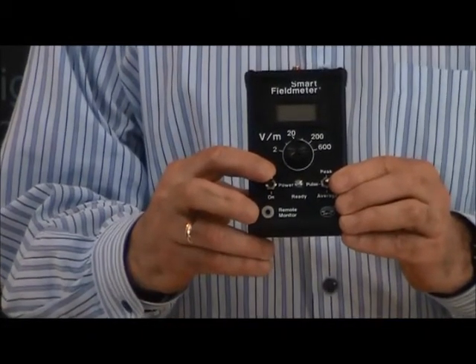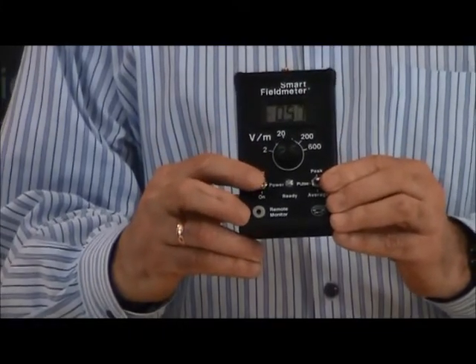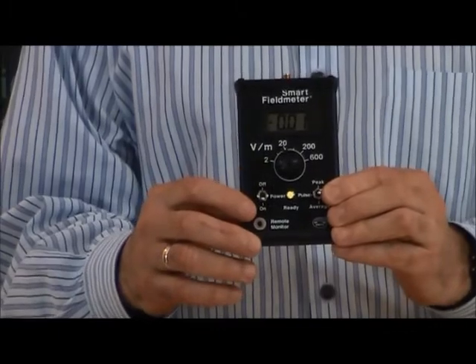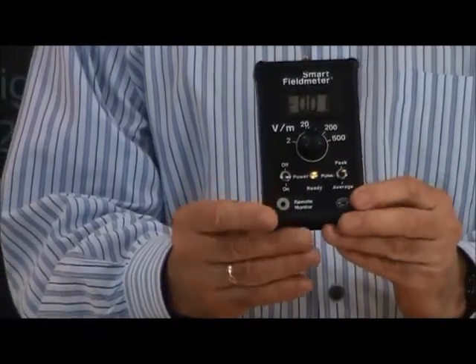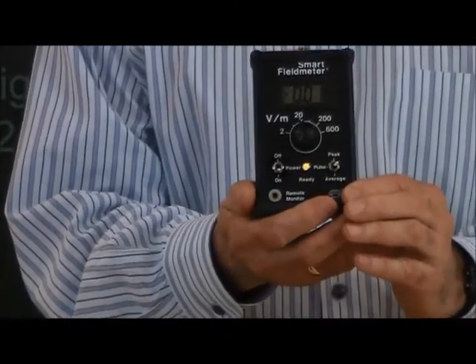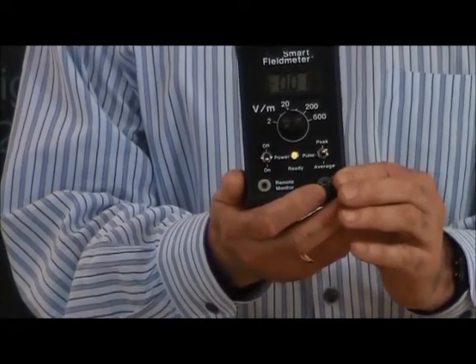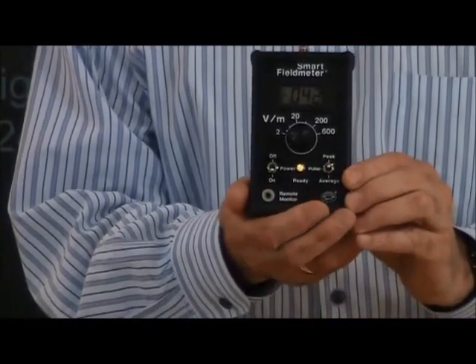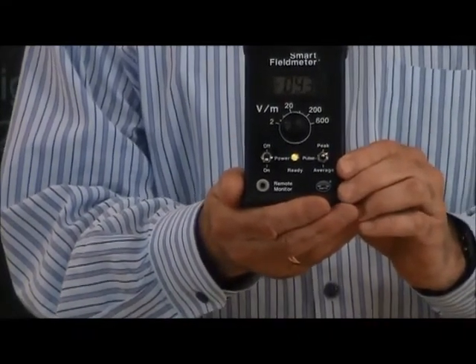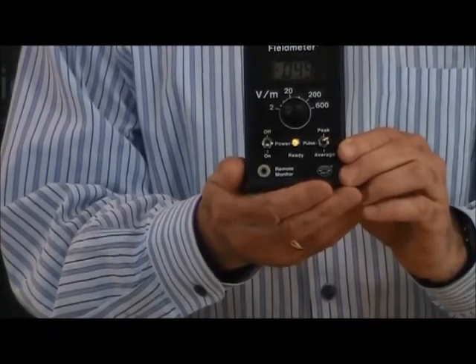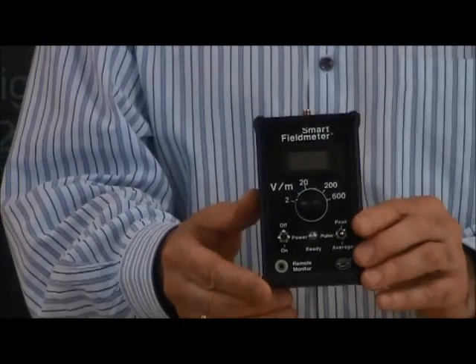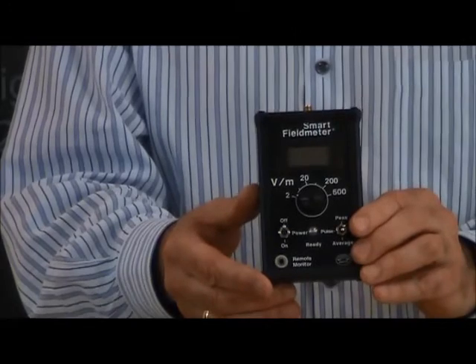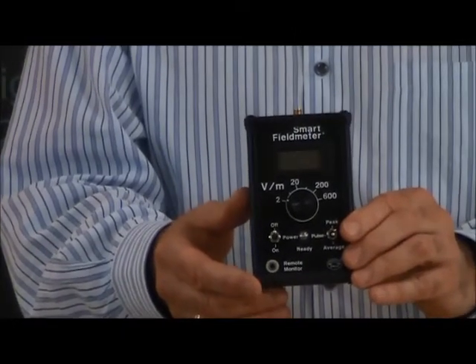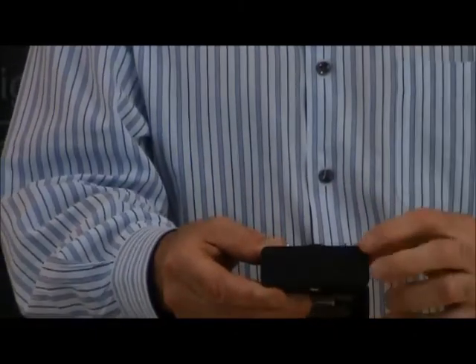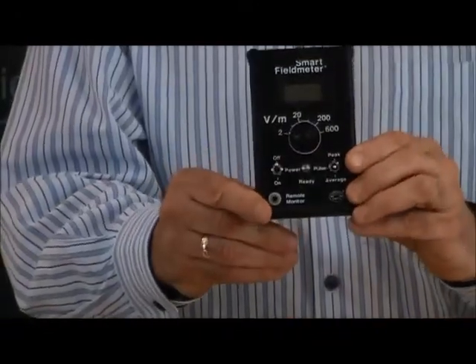This meter has one very unique feature. It's called auto-zeroing. When you turn the unit on, you can see this green light. It comes up not instantly, but after a couple of seconds. This happens because the unit goes through an auto-zero routine that allows you to produce very high accuracy when measuring low fields. When you switch the meter between sensitive ranges, you can see a blink of this green LED, and when the green LED comes on again, it indicates to the user that the unit has been auto-zeroed and is ready for measurements. This unit is powered by a 9-volt battery and it will operate for about 100 hours. So there is no very frequent need to change the battery. If such a need arises, you remove 4 screws from the bottom and the battery can easily be removed and replaced.